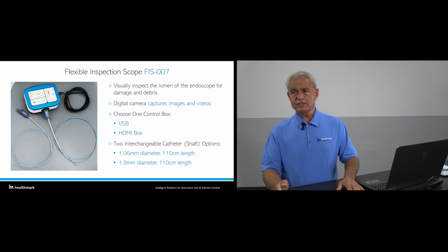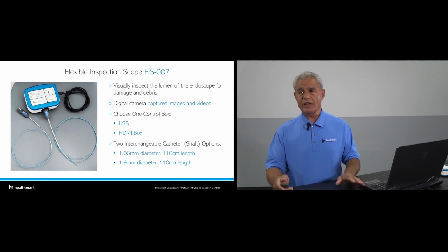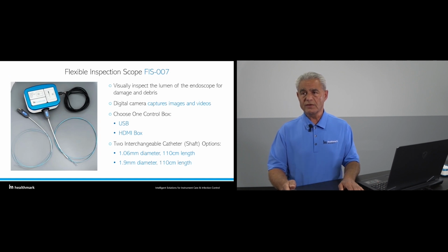Okay, the visual inspection we talked about, enhanced visual inspection, we've been working on for flexible endoscopes for more than a decade. As you see, FIS-007 is our 7th generation of flexible inspection scope. It allows you to visually inspect the lumen of the endoscope for damage or debris. The distal camera captures images and videos for further review.